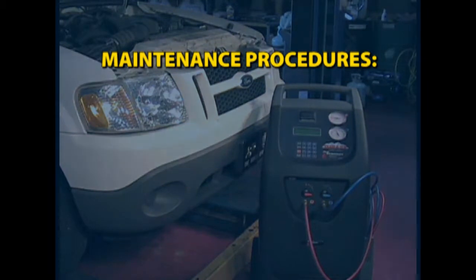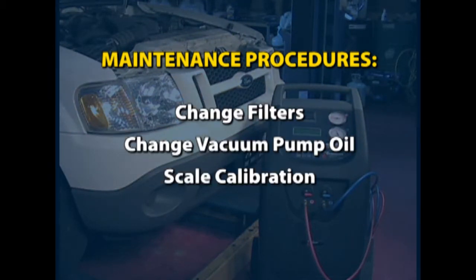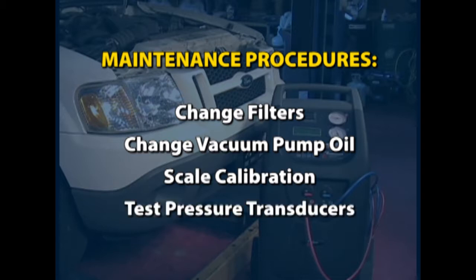Maintaining your CCST388 includes changing filters, vacuum pump oil, testing the scale, and pressure transducers. Your CCST388 warns you when the filters are coming due for a change. Order your filters upon first notification and install them when the machine indicates service alarm. Follow the procedure detailed in the operations manual to replace the filters. Replace the vacuum pump oil when it's visually cloudy or when the filters are changed.